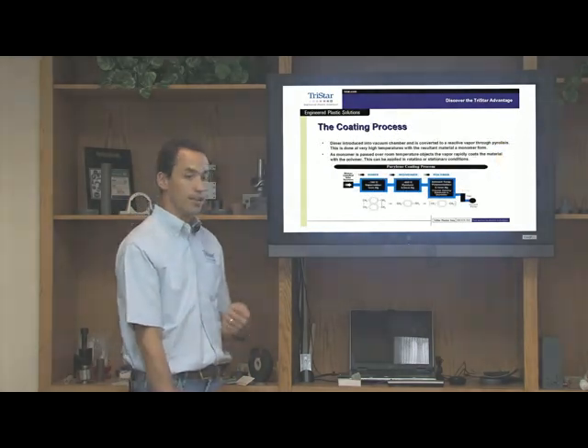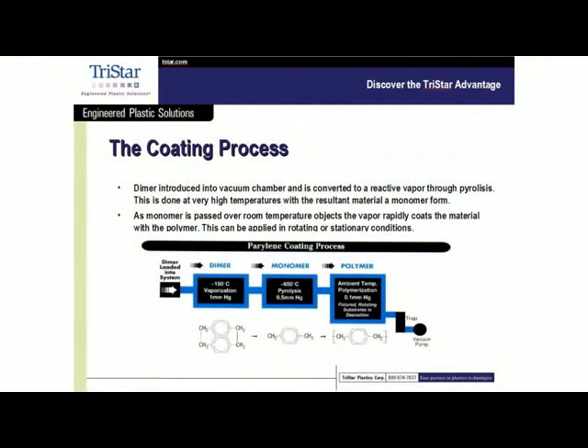The coating process is actually quite simple. Parylene precursors are sold as a solid crystal, which is placed into a vaporizer. The parylene precursor never becomes a liquid — it actually sublimes from solid to vapor, and when it's depositing on material, it goes from vapor to solid. So there is no dripping, there is no pooling. It's fully conformal and gets into every nook and cranny of that device.